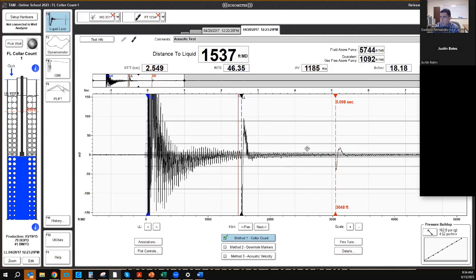It's a down kick, the rest are down kicks. They have smaller and smaller amplitude, so the size is decreasing because the energy is dissipating, and they occur at the same time difference. So these three things are compliant, so we check the box: it's all down kicks, same time difference, and the amplitude is decreasing, smaller and smaller until we can't hear it anymore.